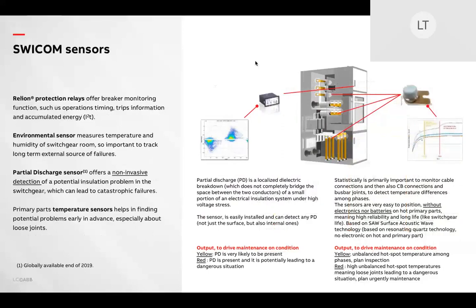Secondly, we have partial discharge sensors that can be applied either by capacitive coupling technology, which is ideal for IEC equipment, as capacitive voltage dividing sensing is a standard feature on IEC equipment. For ANSI or NEMA equipment, we have temperature and ultra-high frequency detection that is used, again, to find the partial discharge sensor. What we're looking for in terms of sensing is anything greater than 100 PD.